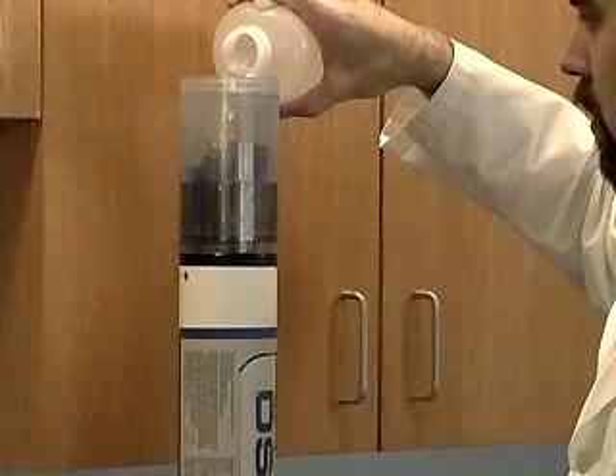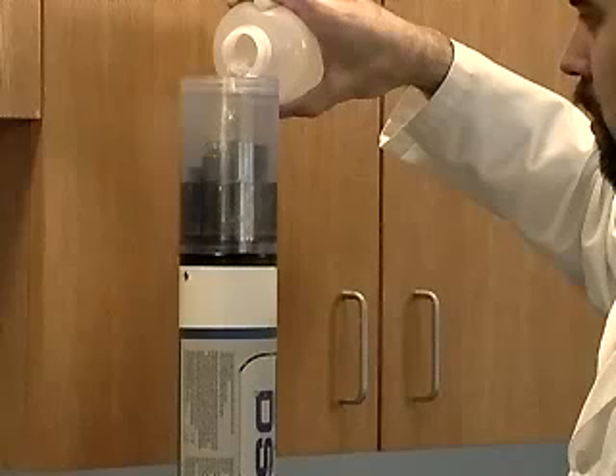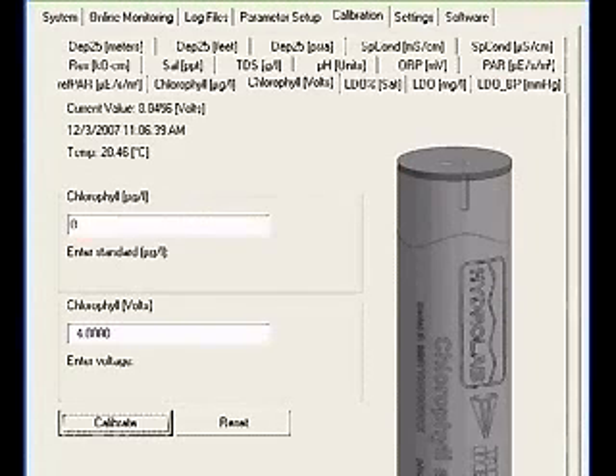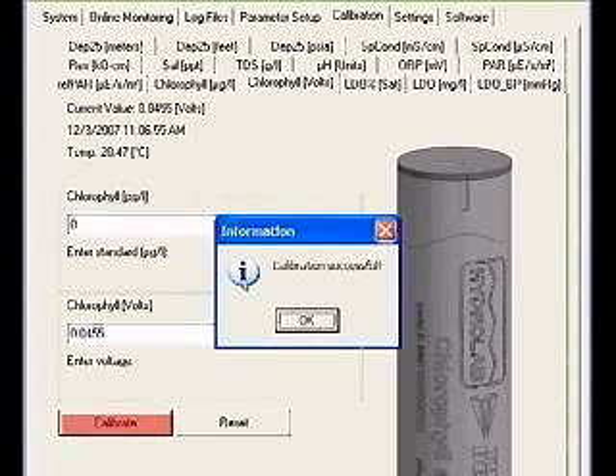When the results of the extraction are known, the chlorophyll A sensor is recalibrated using this value. Type 0 into the box labeled Chlorophyll Micrograms per Liter. Type the voltage from the original 0-point calibration in the box labeled Chlorophyll Volts. Click the Calibrate button. A calibration successful message will appear.